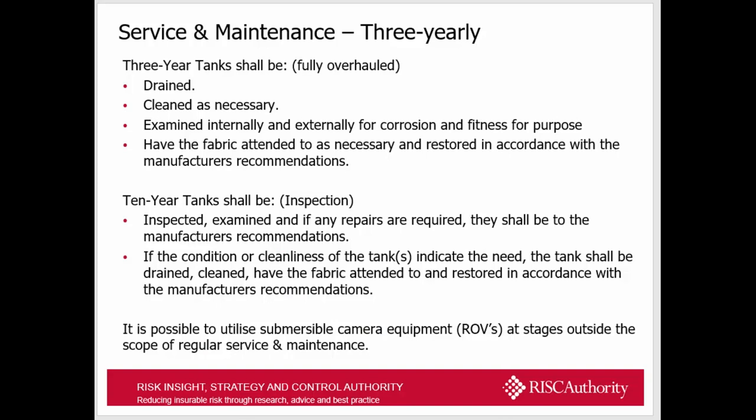Three-yearly tanks shall be fully drained, cleaned as necessary, examined internally and externally for corrosion and fitness for purpose, and the fabric attended to in accordance with the manufacturer's recommendations. For a 10-year maintenance-free tank, it shall be inspected on a three-yearly basis in accordance with the manufacturer's recommendation. However, if the condition and cleanliness of the tank indicates a need, the tank should be drained, cleaned, and have the fabric attended to accordingly.